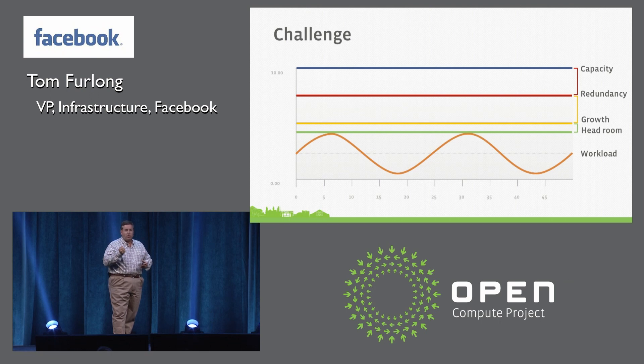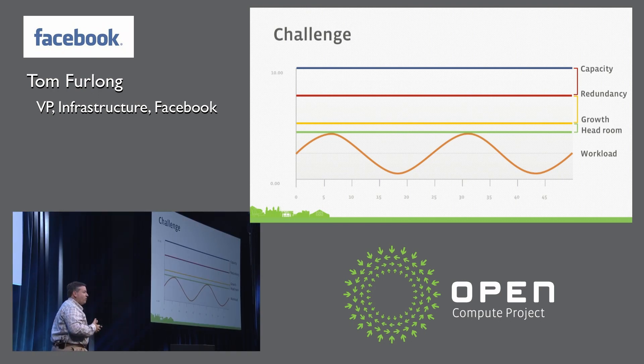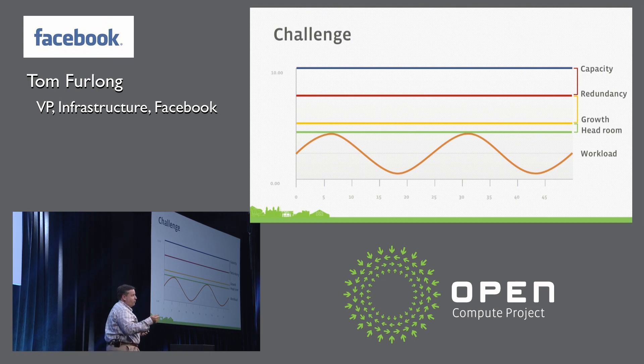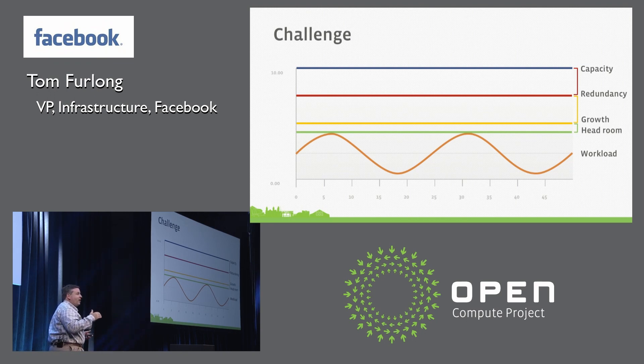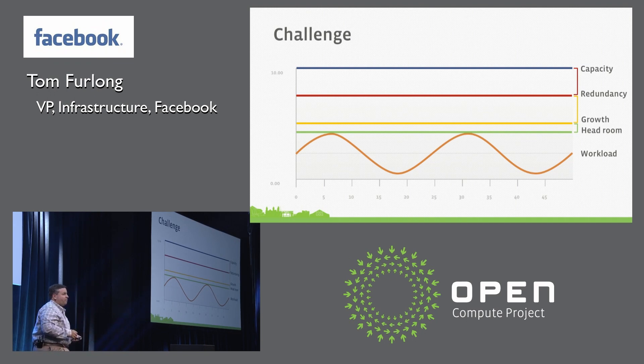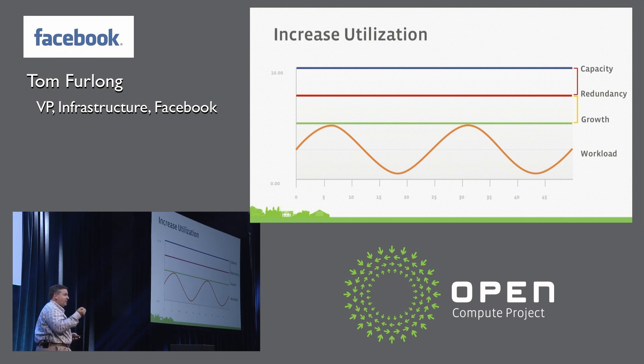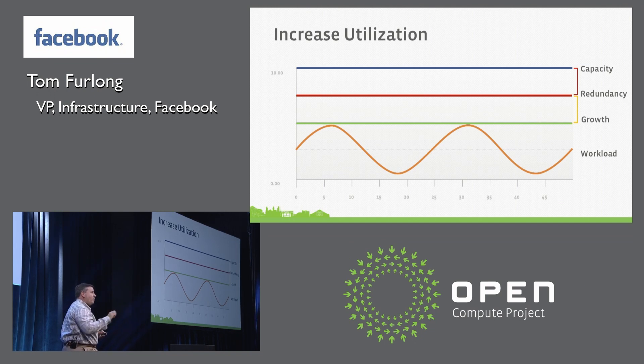When we launch products we don't always know exactly what they're going to need, or if user adoption is faster than we think, we may need to add hardware — so we try to put some provision for growth in there. Lastly, you have a little headroom, or buffer, or reserve, that protects you from exceeding your capacity threshold. When you exceed it in the data center world, you end up tripping blade breakers and machines go offline. If you're able to increase your utilization by reducing that buffer, you can actually get more workload into your data center.